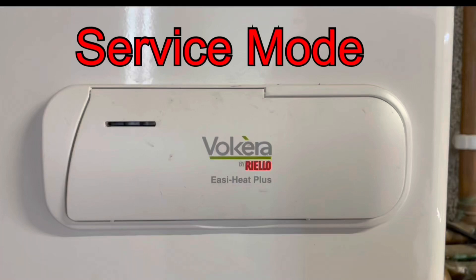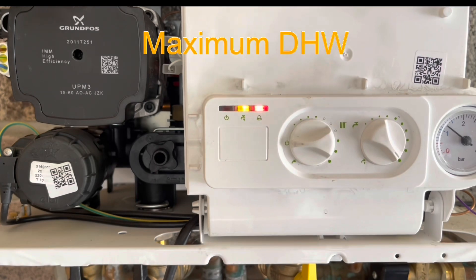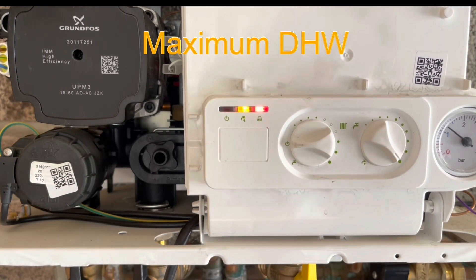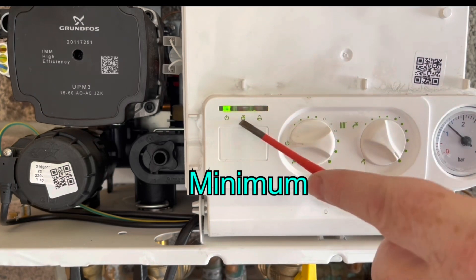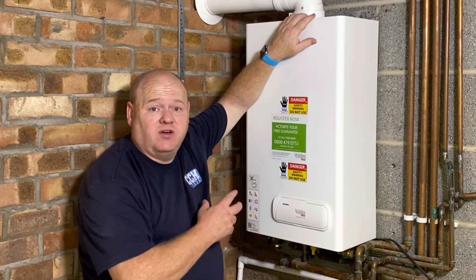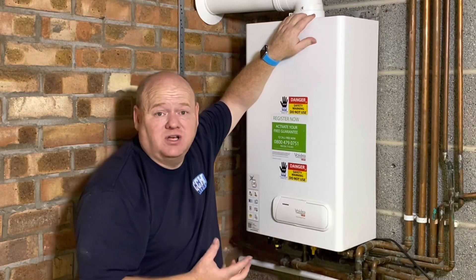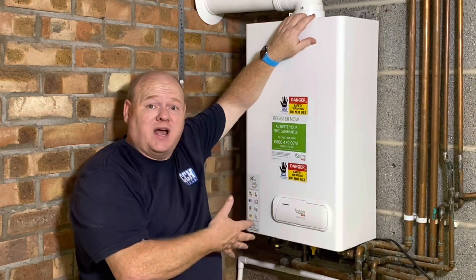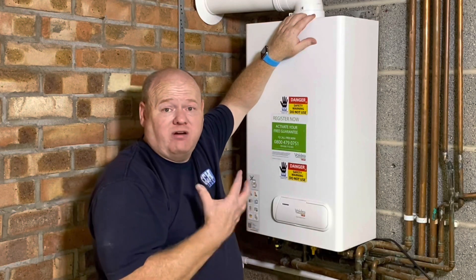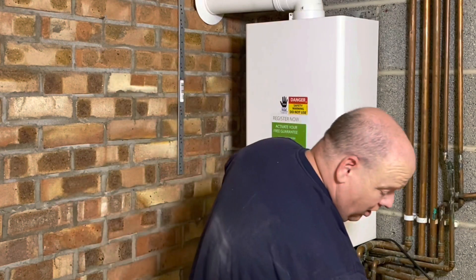How to put a Vokèra boiler into service mode - put it into maximum for heating, maximum for domestic hot water, and then also minimum for your flue gas analyser. My name is Alan Hart and in today's video, a really short video to show you how to put the Vokèra Easi-Heat into service mode for your flue gas analyser - high and low - so you can get the correct readings when you're going to do a service on one of these boilers. I also wanted to show you about the importance of doing a service correctly.